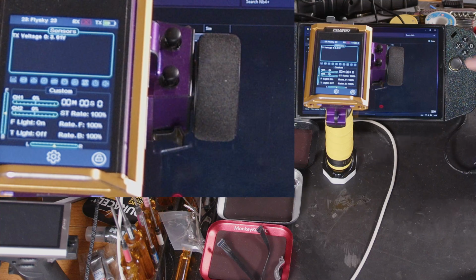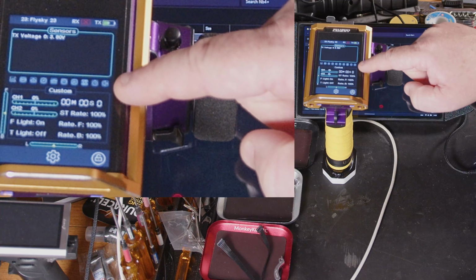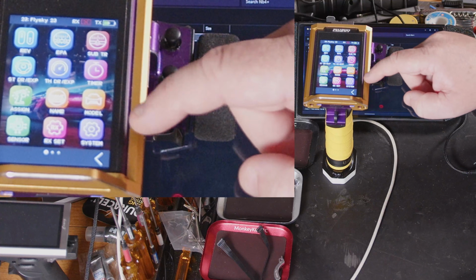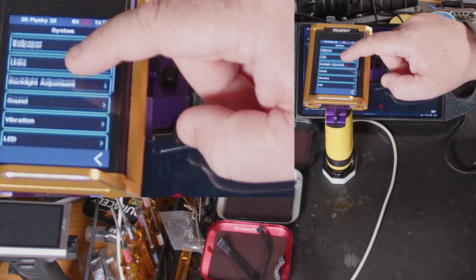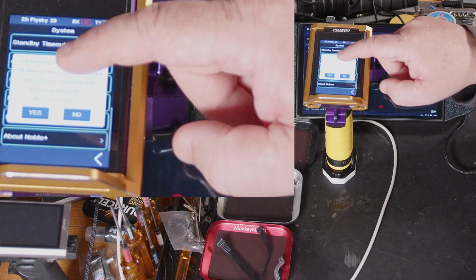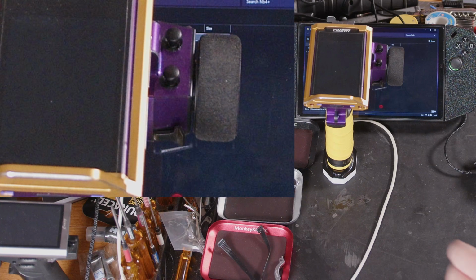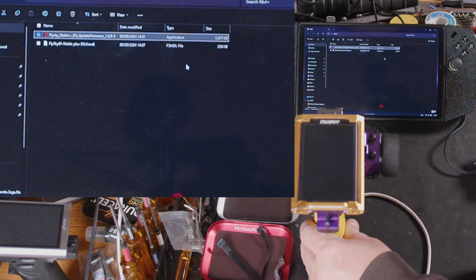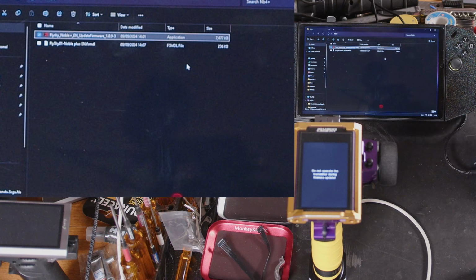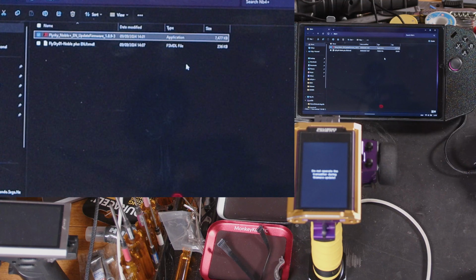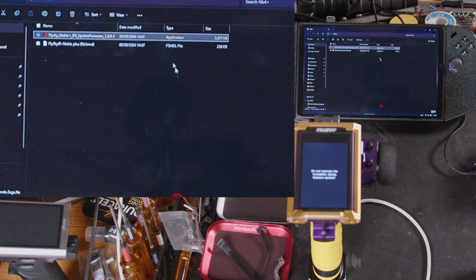So once we've got the firmware update in the folder, we can get the transmitter. We can go to our system menu, scroll down, and then you'll see firmware update. Put it into firmware update mode. You'll hear Windows detect it. You'll see it comes up on the transmitter saying do not operate.